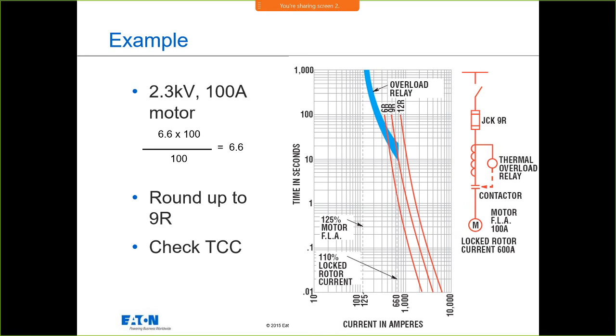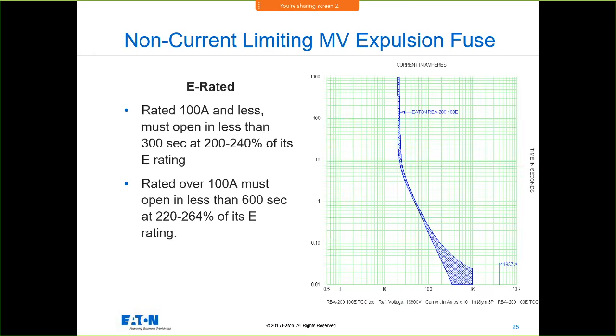There's your overload relay. You're going to want to plot those together. You have your 110% locked rotor amps and your 125% full load, and in between these two data points you could pretty much draw your start curve. You just want to make sure that you pick a fuse that will let that motor start, and you let your overload elements do their job in protecting the thermal capabilities. And there's your E-rated 100 amps. That's basically what she looks like.